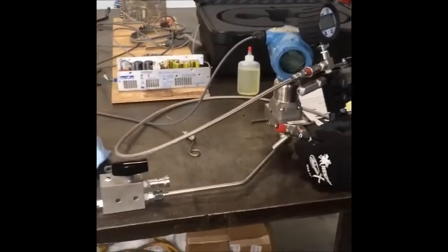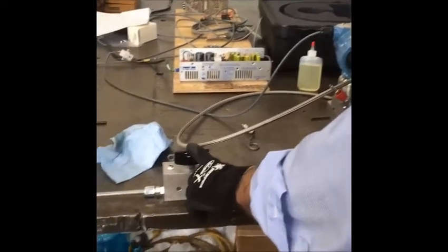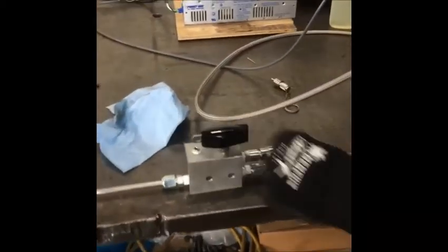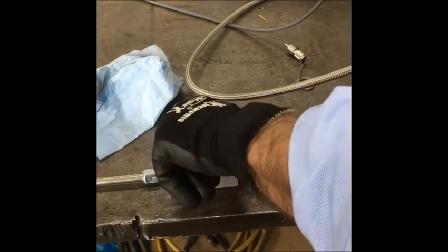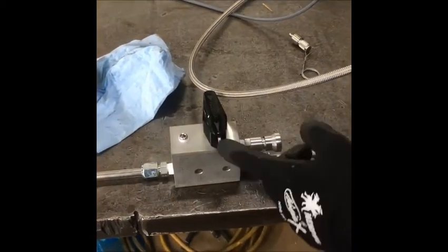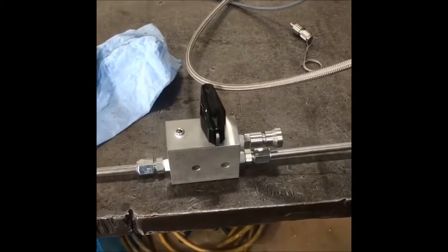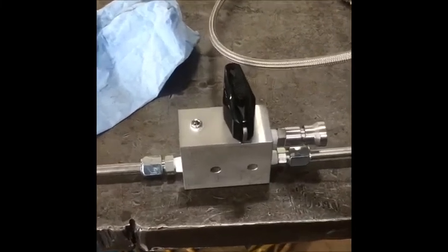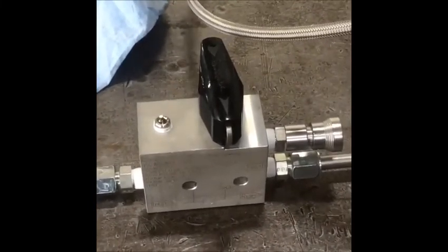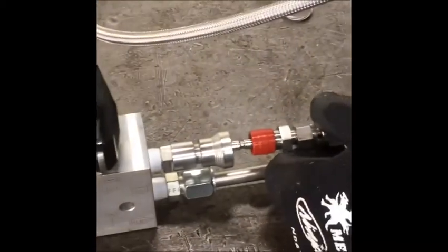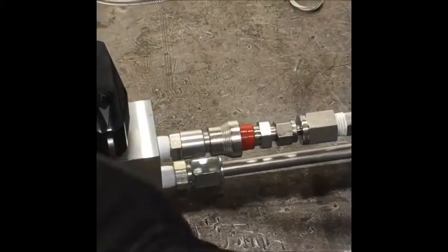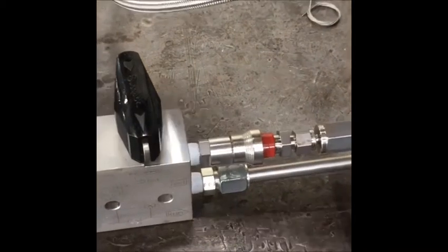Now we're going to recommend that at that point the test block be switched from the run position, which is this way, to the test position, which is this way. To release the block, you just push in on the little locking mechanism. So now it's in the test position, and now we'll engage the quick connect into this device. And also it clicks when it locks in.